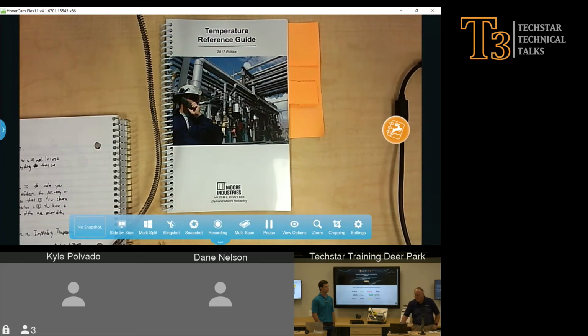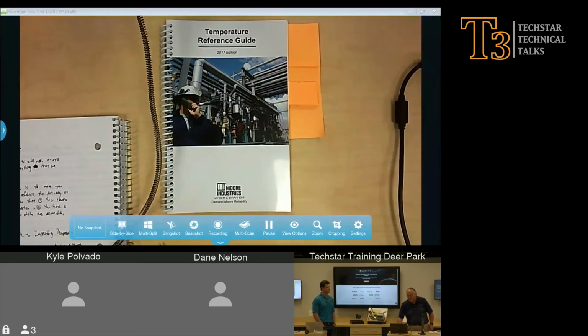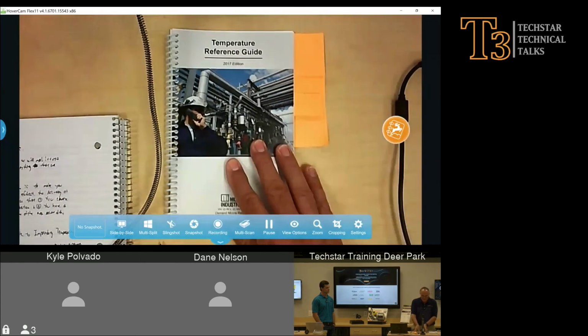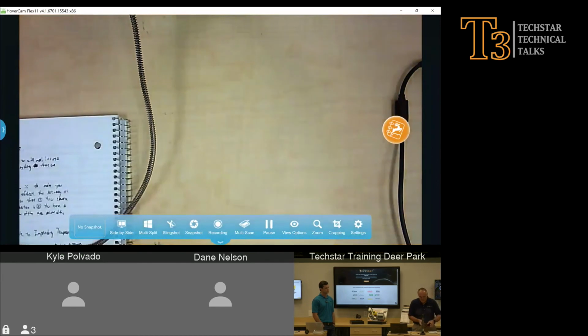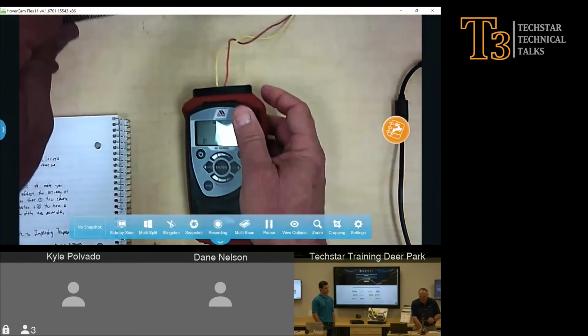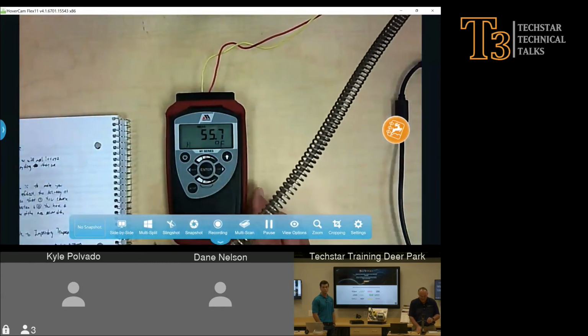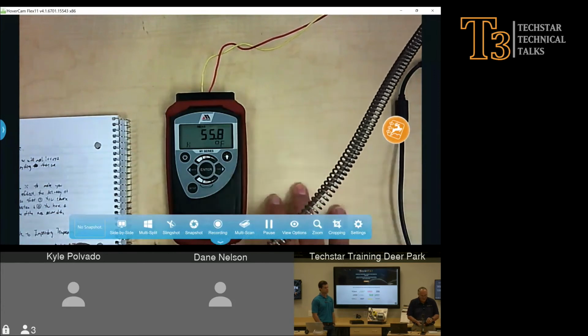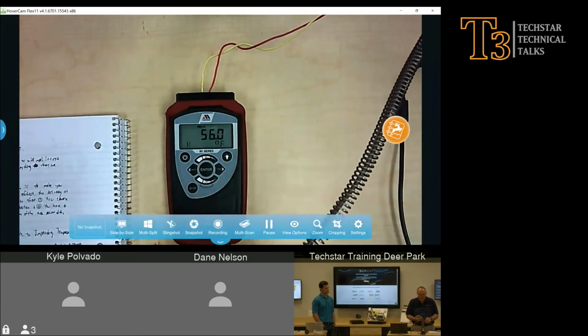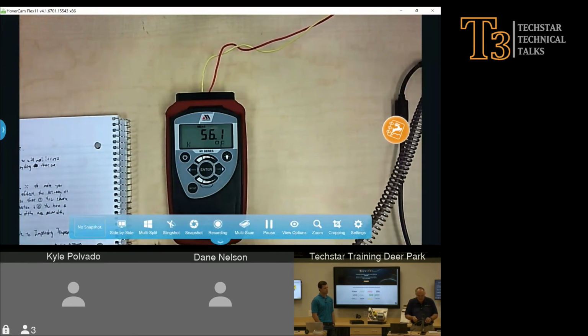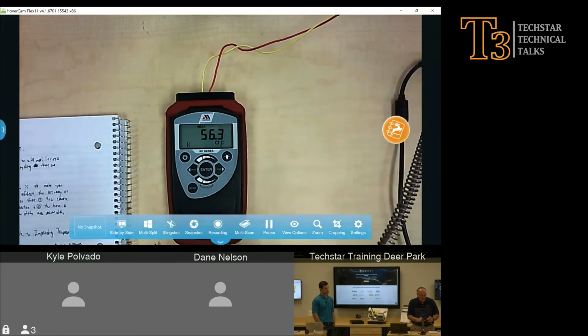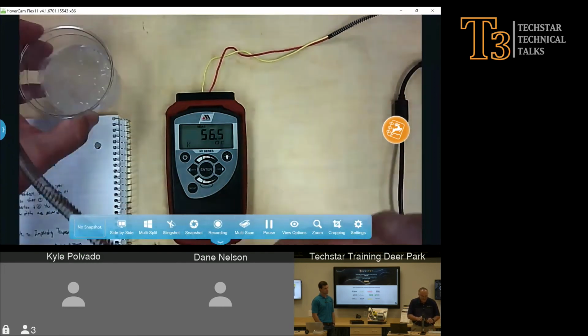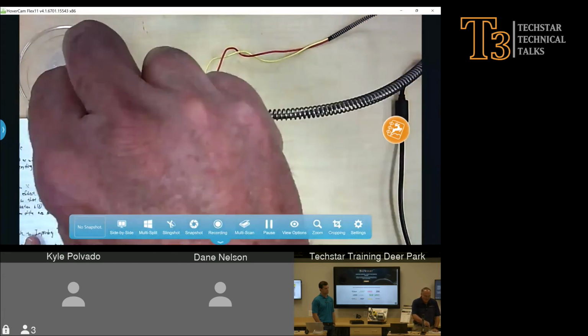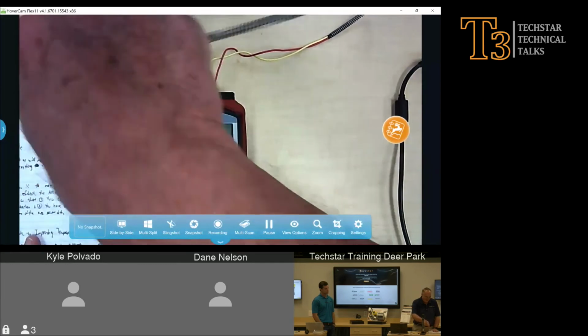So what I was going to try to show, let me see how this works. So here's a reference. It's amazing what you can do with a voltmeter and some ice. So what I've got is a type K thermocouple and a thermocouple simulator. The difference between this little red box and my Fluke meter is this has a built-in cold junction reference. When you're looking at a thermocouple, you have to have two dissimilar metals with two junctions, and the millivolts flow based on the delta T. So the easiest thing that we have is almost all the temperature curves. By the way, I don't want anyone to leave without at least knowing how to read one of the RTD curves, but I just put this in here, and this should be reading 32 degrees.